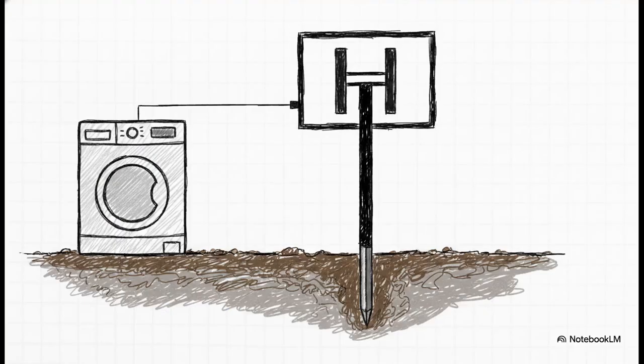To guarantee this escape route actually exists, the MEN system acts as this beautifully interconnected network. It's carefully designed so that a fault anywhere in the building has a direct highway straight back to the source to trip the breaker. According to Clause 5.3, we need some really specific, mandatory parts to physically build this out. We need the earth electrode, which gets driven deep into the soil. We need the main earthing conductor connecting the board to that electrode. We need the protective earthing conductors. Those are the green and yellow wires running out to your actual appliances. And finally, the MEN connection itself, linking the earth bar to the main neutral conductor right at the switchboard.